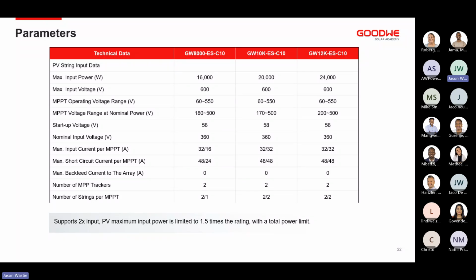We've seen with other inverters, your operating voltage will probably only be around 120 volts. So you get additional PV production time much earlier, or when the PV panels are not drawing as much as 120 volts. So you could start producing 20 minutes, 15 minutes, half an hour earlier, and until later in the day or on a cloudier day.